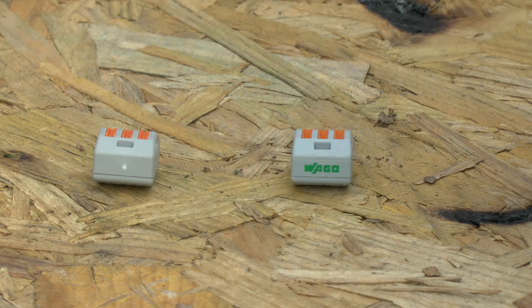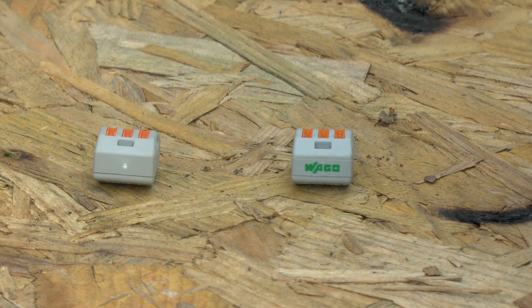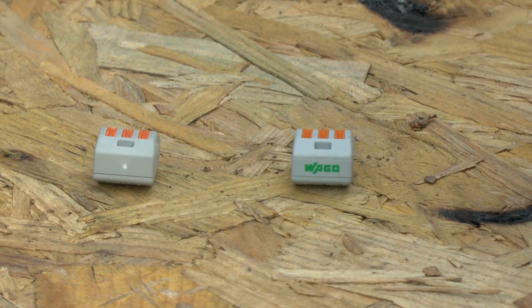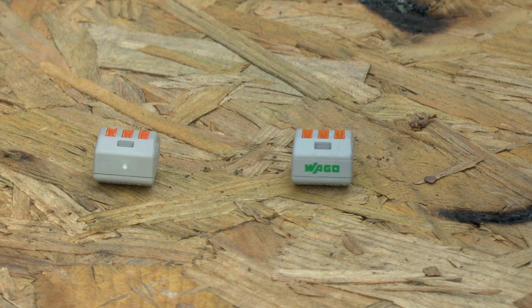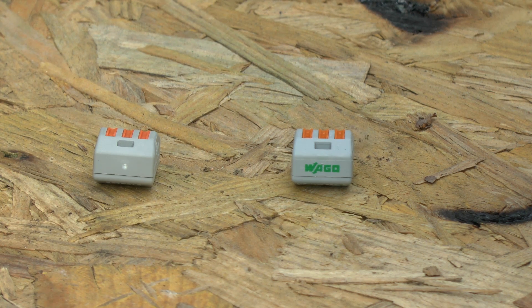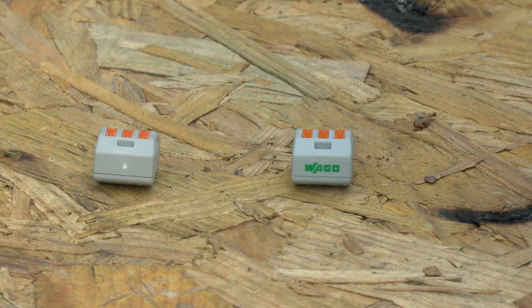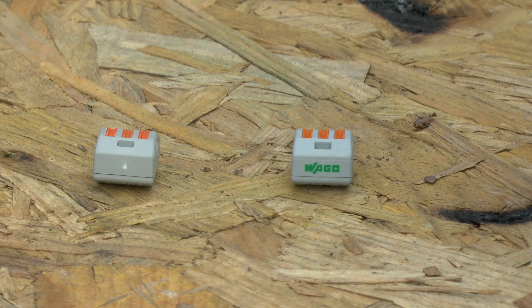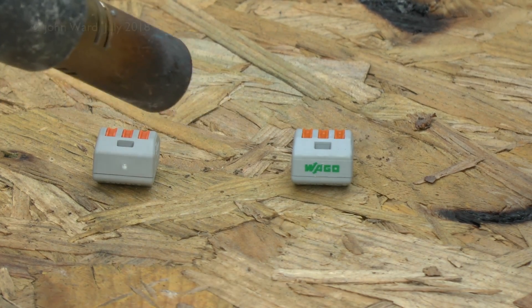Now for the first test, we're going to apply a flame to these and see what happens. Now we're doing this outside, obviously. Unfortunately, it's a windy day, and also the sun keeps going in and out as well. So the lighting might go a bit wrong on some of these, but that's just how it is. Now if these things actually burn, what should happen is that when the flame is removed, they should self-extinguish. So we're just applying the flame there to the WAGO one.